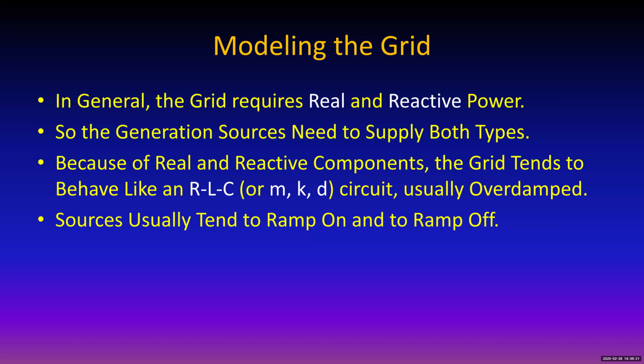Sources generally tend to ramp on and ramp off, starting up relatively slowly. Even solar inverters are oftentimes programmed and designed such that they don't turn on instantaneously - it takes them a little while to turn on.